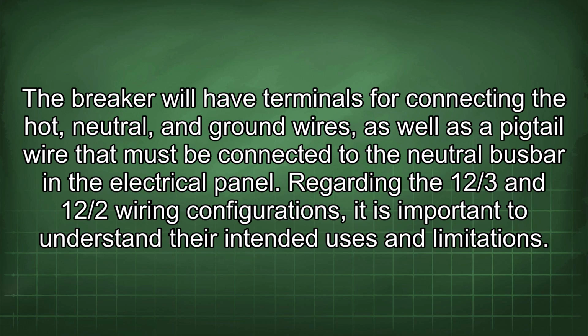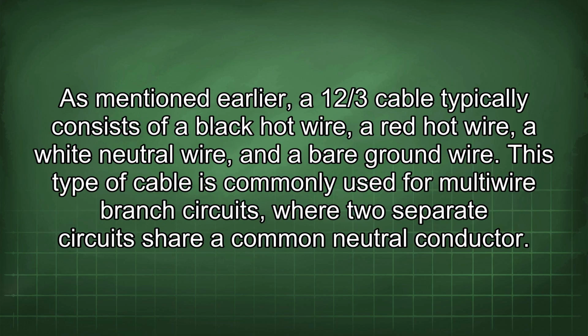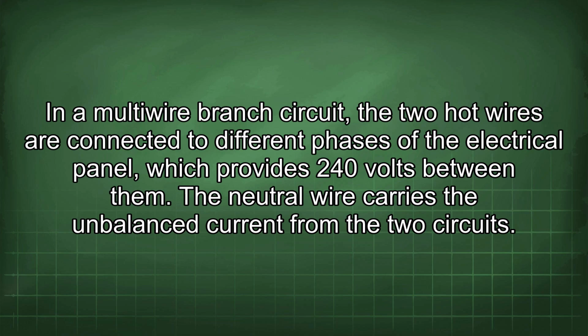Regarding the 12/3 and 12/2 wiring configurations, it is important to understand their intended uses and limitations. As mentioned earlier, a 12/3 cable typically consists of a black hot wire, a red hot wire, a white neutral wire, and a bare ground wire. This type of cable is commonly used for multi-wire branch circuits where two separate circuits share a common neutral conductor. In a multi-wire branch circuit, the two hot wires are connected to different phases of the electrical panel, which provides 240 volts between them. The neutral wire carries the unbalanced current from the two circuits.